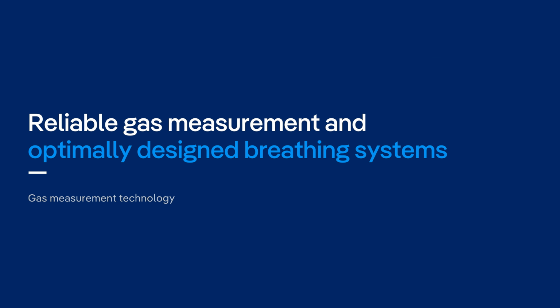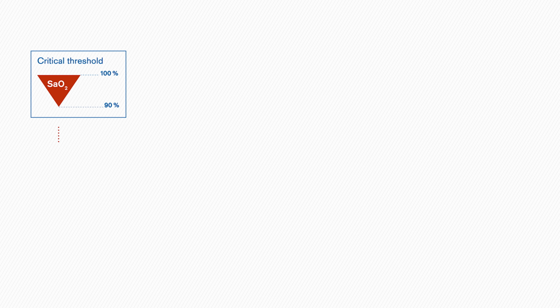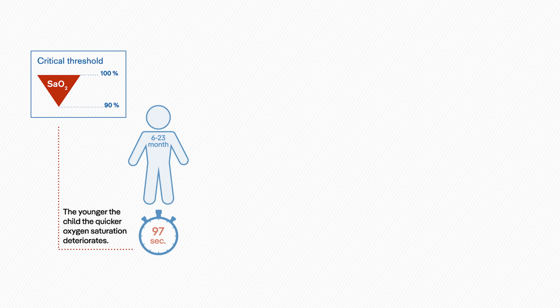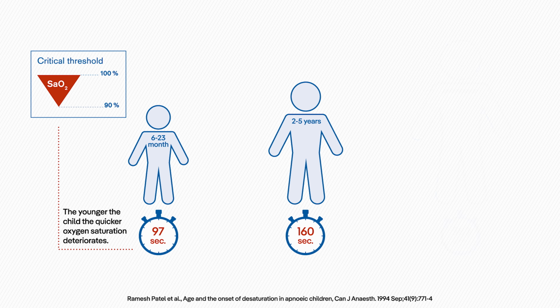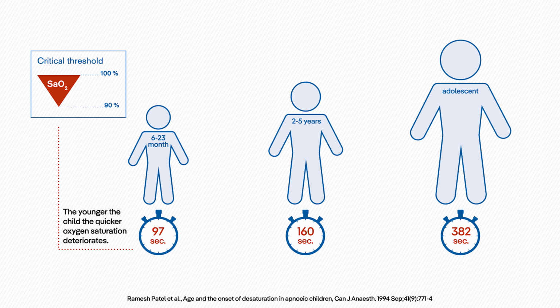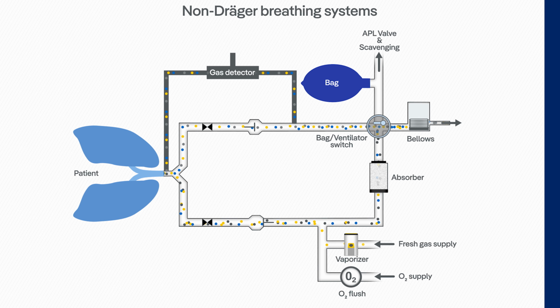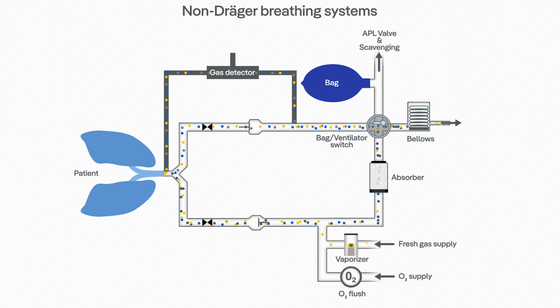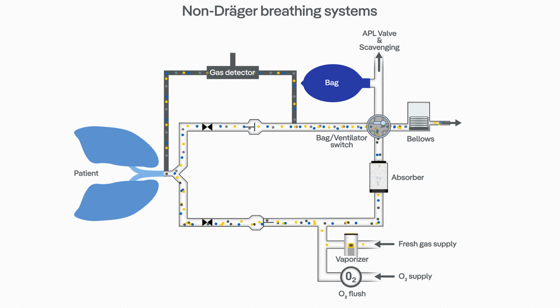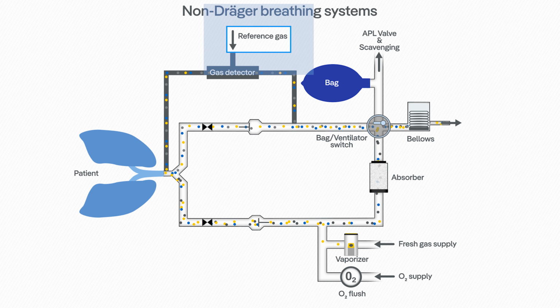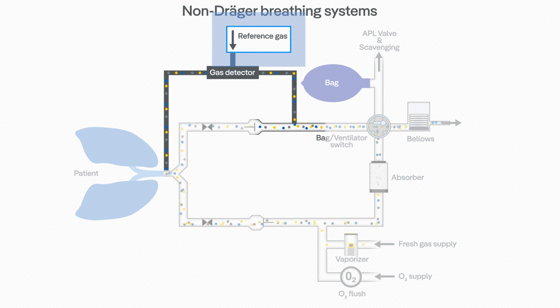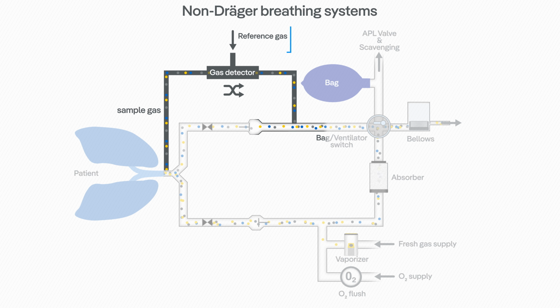Children desaturate very quickly, and the younger the child, the quicker oxygen saturation deteriorates. In children, a reliable measurement of gases, especially oxygen, is crucial. For oxygen measurement, different technologies are available on the market. Depending on the technology used, some of the anesthesia devices require a reference gas for precise measurement. This technology implies that the sample gas extracted from the breathing system is mixed with a reference gas, which has a different composition than the gas mix in the breathing system.